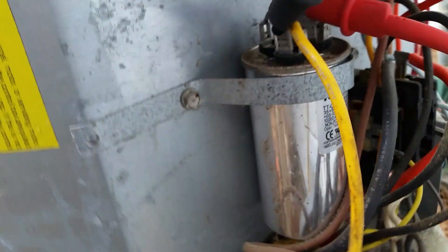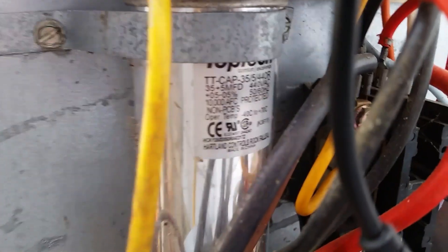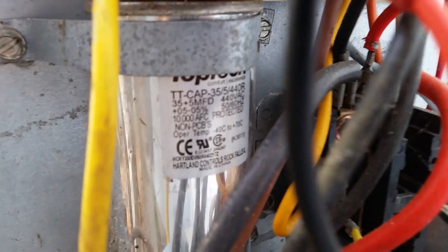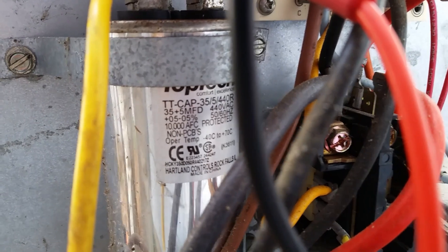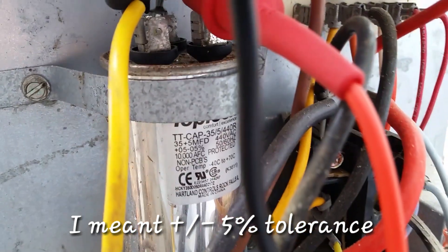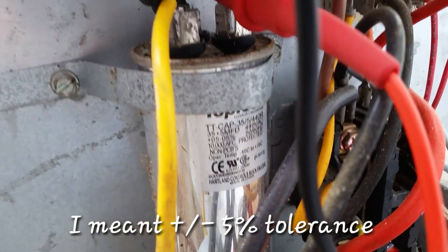Hopefully you can see it. This capacitor is rated 35 plus 5 µF and it has a tolerance of plus or minus 0.5. So that capacitor under load is weak.